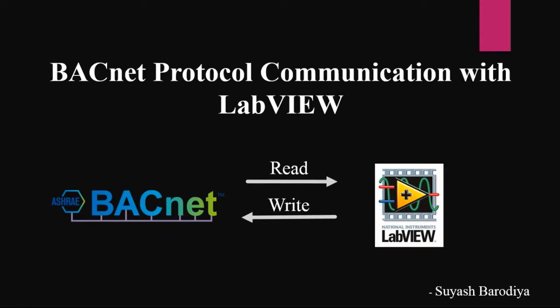Before initiating the actual task, let's talk about some basics of write properties. The write property service is used by a client to allow the user to modify the value of a single specified property of a BACnet object. This service potentially allows write access to any property of any object, whether it is a BACnet defined object or not.